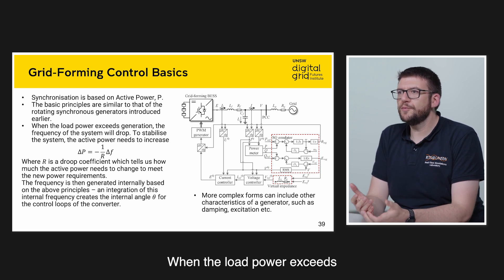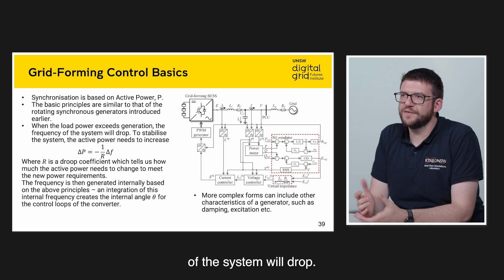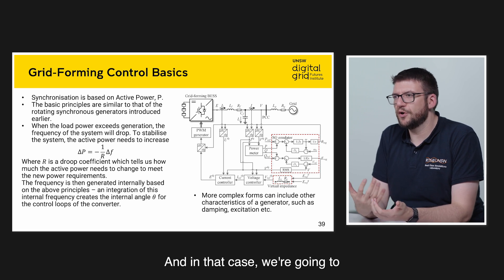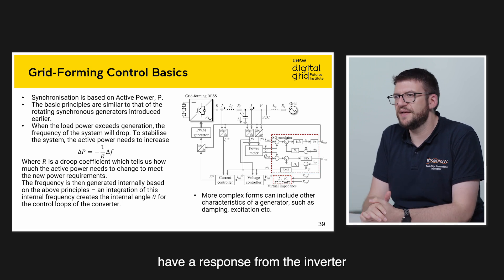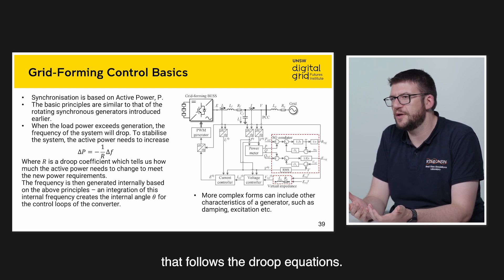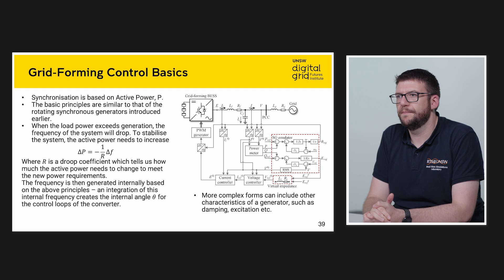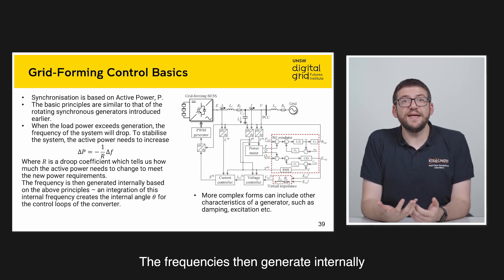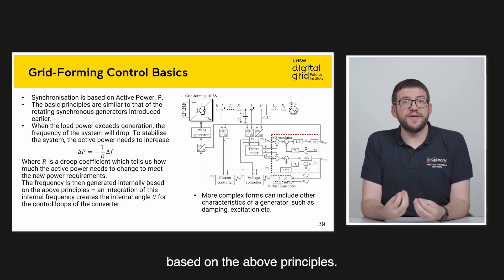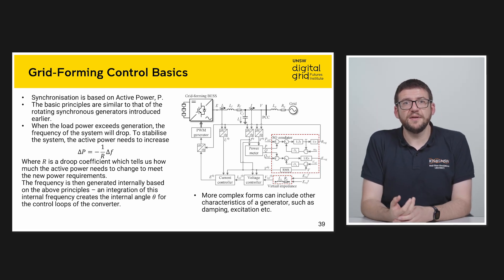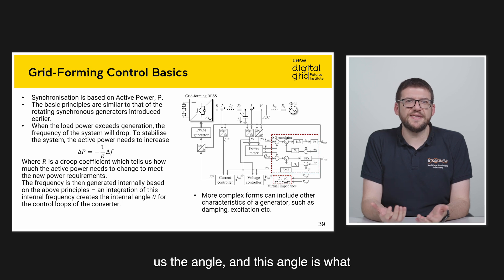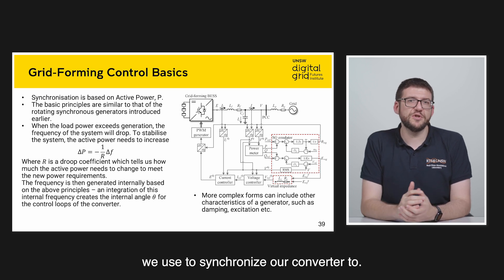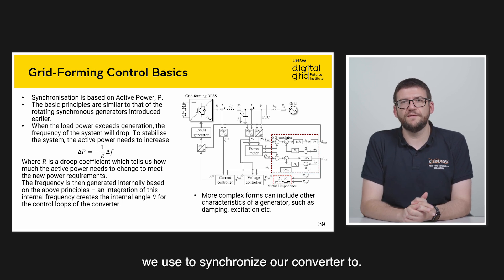When the load power exceeds generation, the frequency of the system will drop, and in that case we are going to have a response from the inverter that follows the droop equations. The frequency is then generated internally based on these principles. The integration of the frequency gives us the angle, and this angle is what we use to synchronize our converter to.